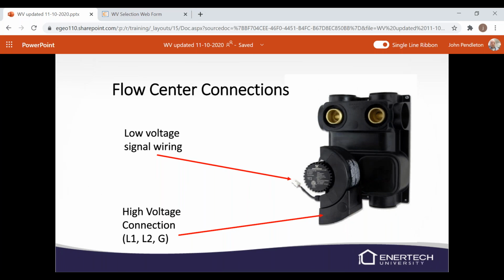The low voltage connection, there's a 15-foot wiring harness that will plug into this MOLEX connector on your pump. If you're ever concerned about a pump, whether the pump is bad or if it's a controller issue with a variable speed pump, just disconnect the low voltage. When you disconnect the low voltage on the pumps, those pumps get confused. They don't know how to operate, so they run at 100%. That's a good way to know if the module on the pump or the motor itself is bad, is just by unplugging that MOLEX connector. Almost immediately, it should start operating and it'll run at 100%.